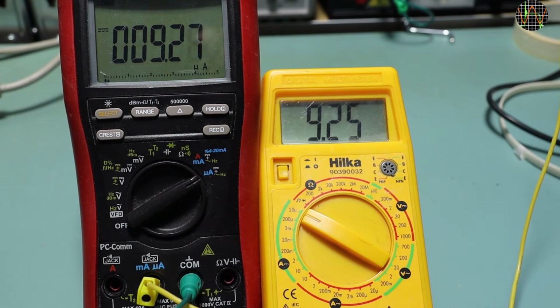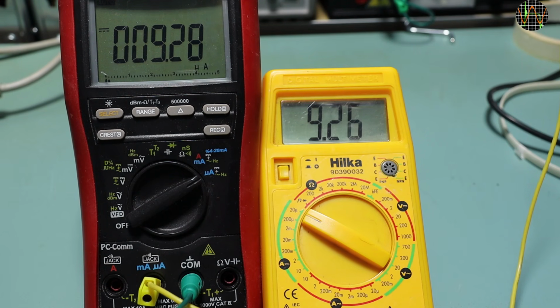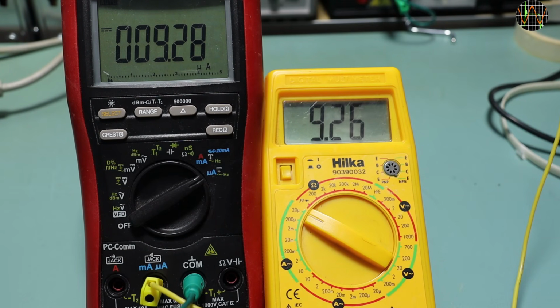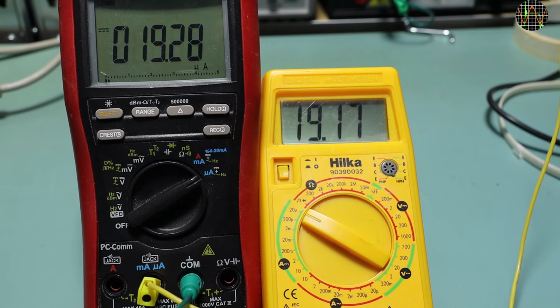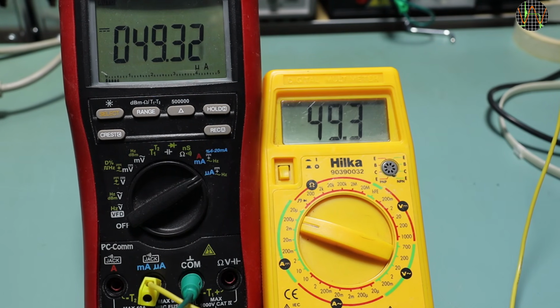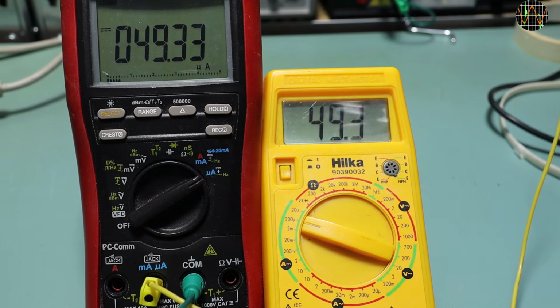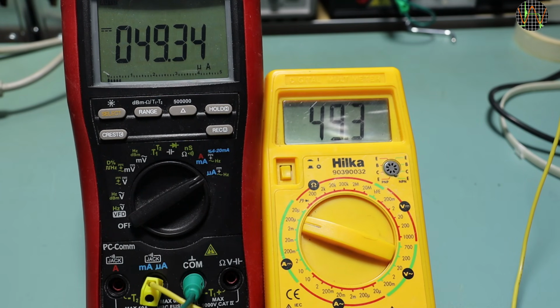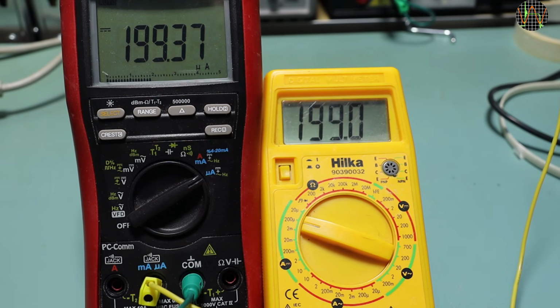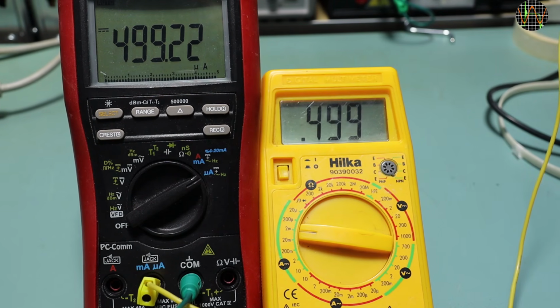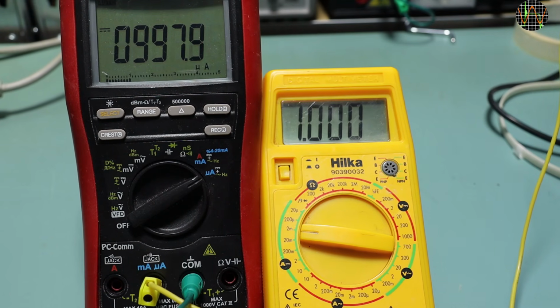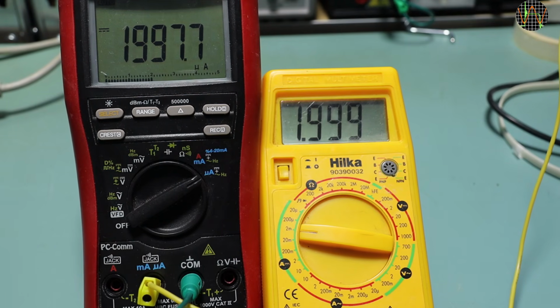DC milliamps, starting with a 20 microamp range and feeding approximately 10 microamps in comparison with the Brymen BM869S. It's very close. About 20 microamps and still close. Switching to the 200 microamp range, 50 microamps and the meters practically read the same. 100 microamps, all is fine. 200 microamps, still very close. 2 milliamps range now. 500 microamps and spot on, 1 milliamp and close, 2 milliamps, same story.